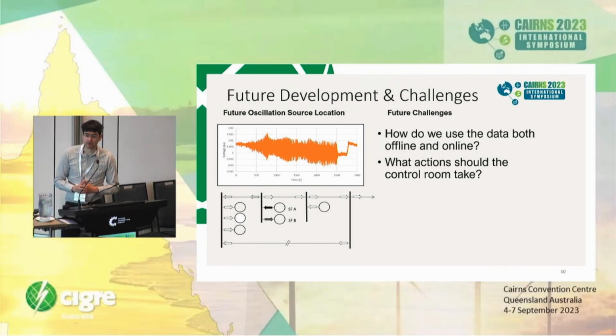Our next development that we're currently looking at is, now that we know we've got an alarm when the oscillations are happening, what do we do next with that information? Well, there's a neat little algorithm that's being developed by ISO New England that will actually use PMU data to narrow down to exactly where the source of the oscillation is coming from. We've been testing this algorithm on simulated and real data, and it's been shown to be highly effective for these kinds of inverter-based oscillations to narrow down exactly which plant is causing the oscillation.